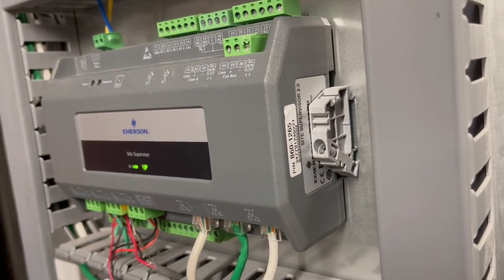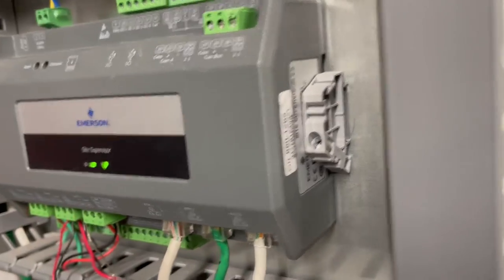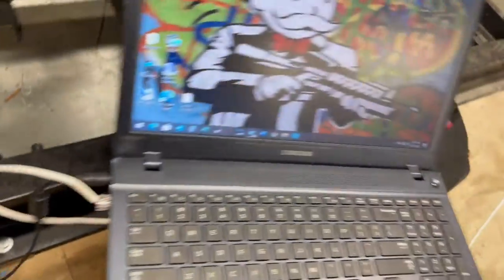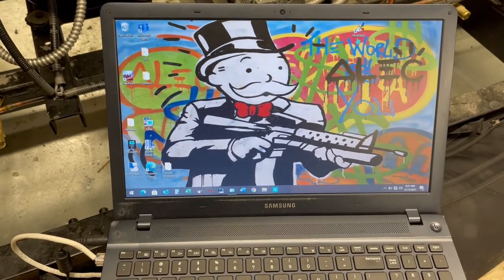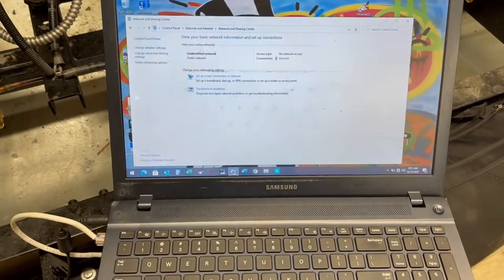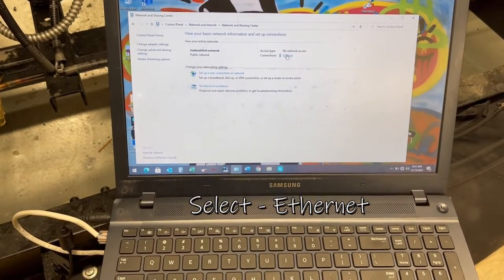To the right of the controller, you have the sticker of the version and everything. We usually write the IP address there for the guys. And right now, I'm gonna go plug into it. You see the Cat 5 wire plugged into the computer. And on the other one, you needed the UltraSite 32 to work to get into the controller to the E2s, but for this one, you don't. All you have to verify is you don't conflict.